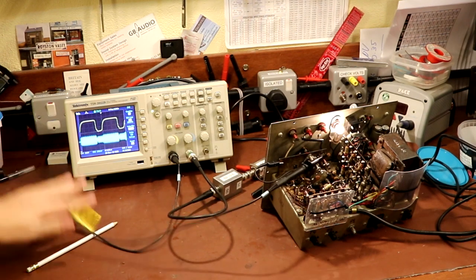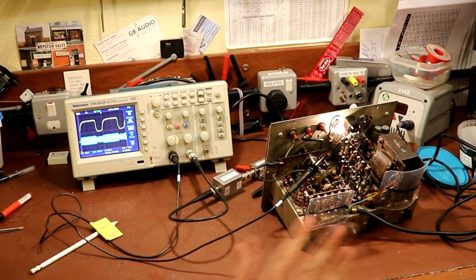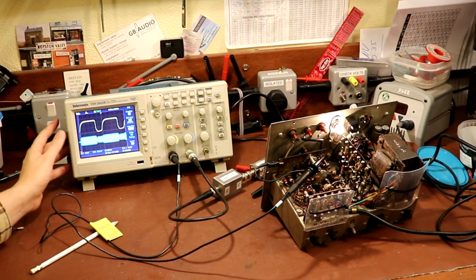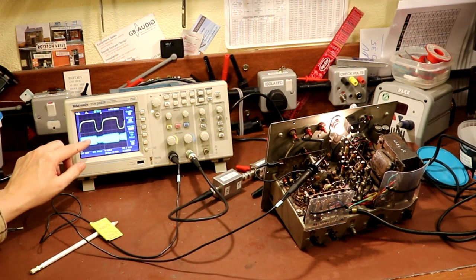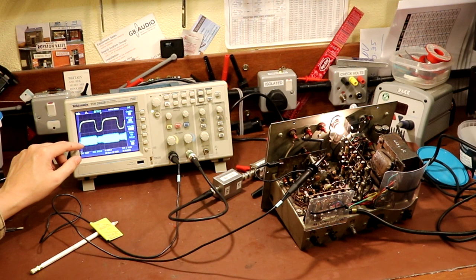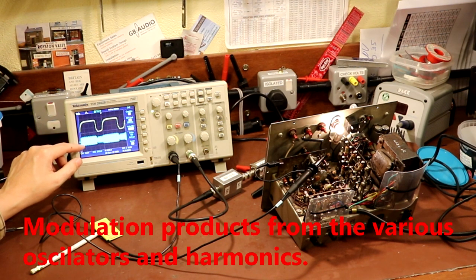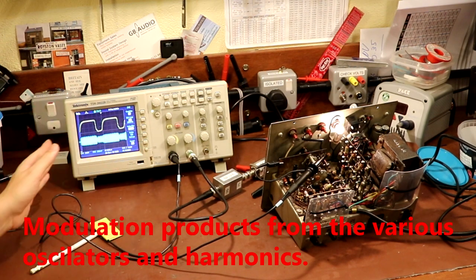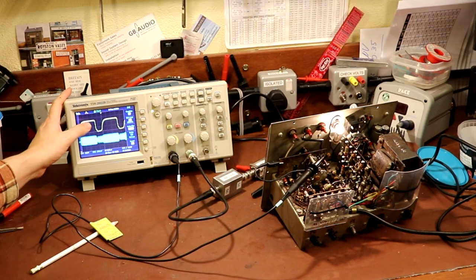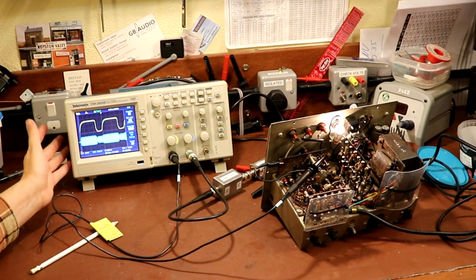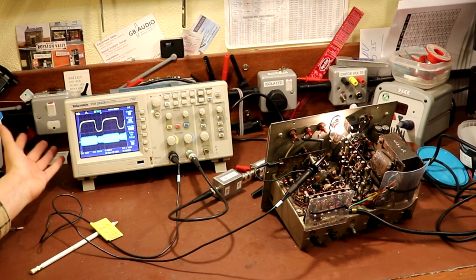Now there is an adjustment on the back of here, so I'm going to go ahead and tweak it up now. You can actually see that my whole bench here is alive with RF. Quite an interesting thing, just being diverted there. You can see there's a lot of shimmer and what looks like noise rippling about on the top of this video waveform. Well, what that's implying is that there's an awful lot of RF energy floating around, a lot of modulation, and some of that modulation is intended, and a lot of it is unintended. But basically it will make the waveform shimmer, and you may find that you can't trigger on it at all. As it happens, I'm triggering on the multivibrator output above, so that's okay. But when you have trouble triggering on waveforms, that's generally because they're complex, and they may be rich in harmonics.